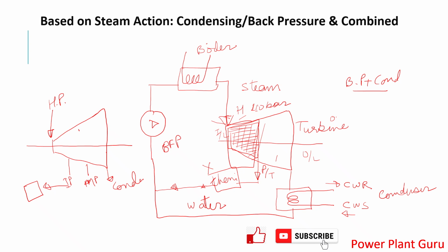Okay, I need to reduce the steam consumption. I need to change the steam consumption into this process. So in that case, you need to have a control valve. And in that case, this type of extraction is called controlled extraction. What we call controlled extraction. So normally this happens in a process plant or chemical plant.